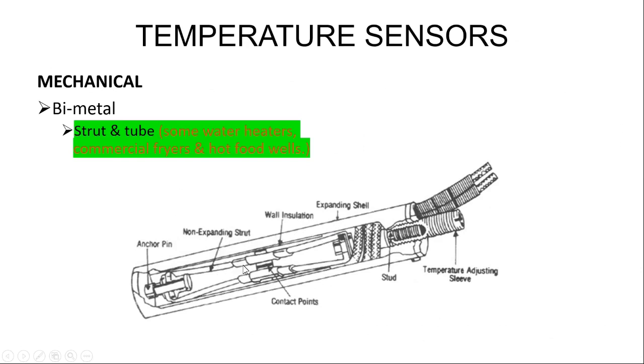A pair of electrical contacts is mounted on the strut assembly and installed in the shell under tension or compression. Each end of the strut assembly is mechanically connected to the ends of the shell, and net change of force is produced on the strut assembly as the shell expands or contracts with changing temperature. The temperature at which the contacts make or break can be regulated by a temperature adjusting sleeve.